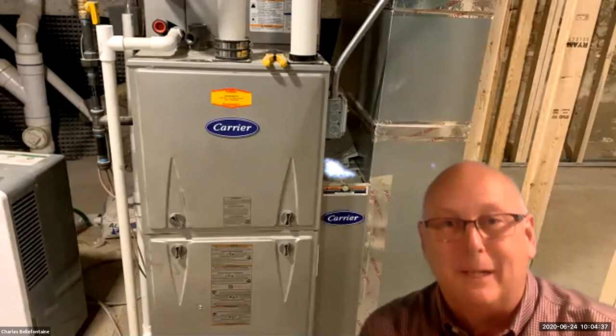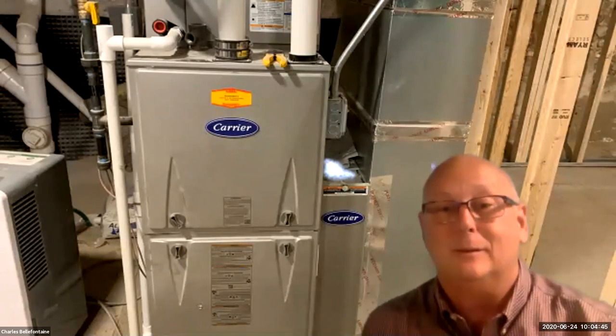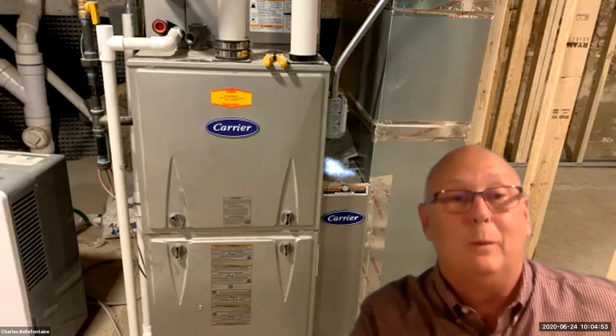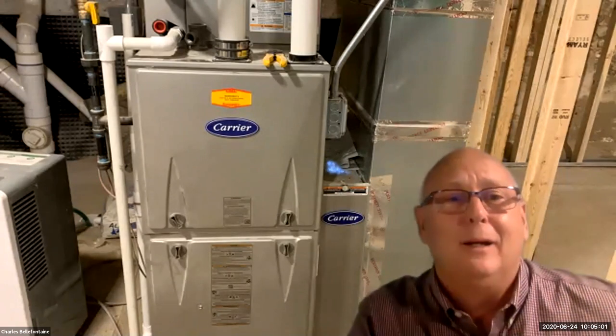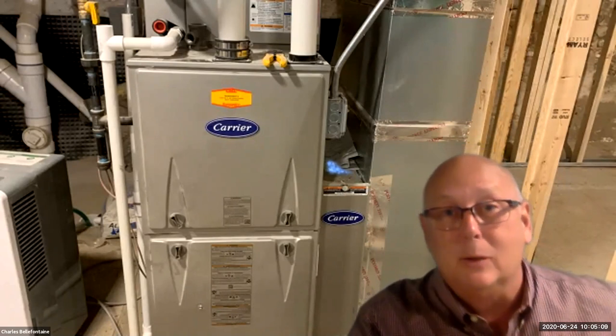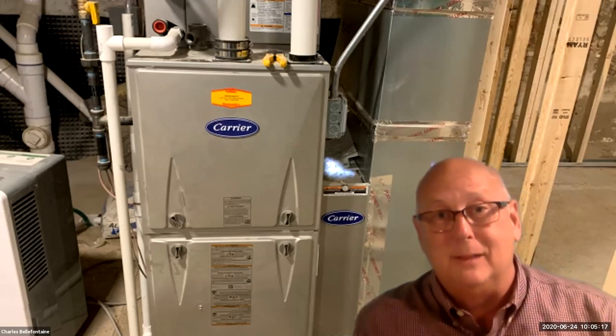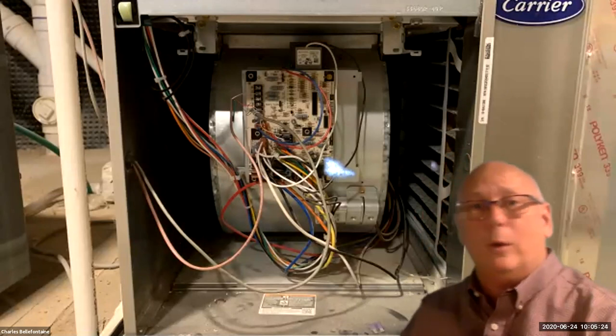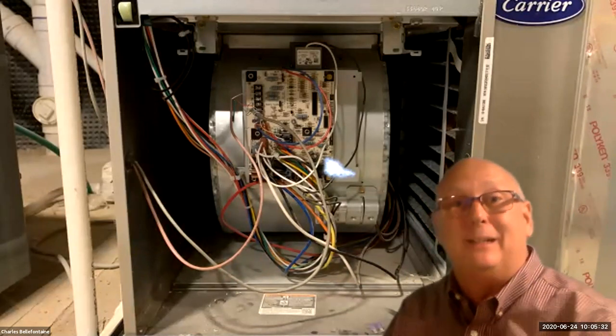My home has a basically less-than-two-year-old high efficiency furnace — that's what's shown in the background. When we do our home inspections we're a little bit more technically exhaustive than most. The biggest problem we're always going to find with a forced air furnace is the cracked heat exchanger or a hole in the heat exchanger — something that makes the unit unsafe. One of the first things I look at is down underneath in the blower fan area. If you can shine a flashlight in there, that area should be dry. It's not a definitive sign of a heat exchanger problem, but rust, condensation, or anything that shouldn't be there is a clue.